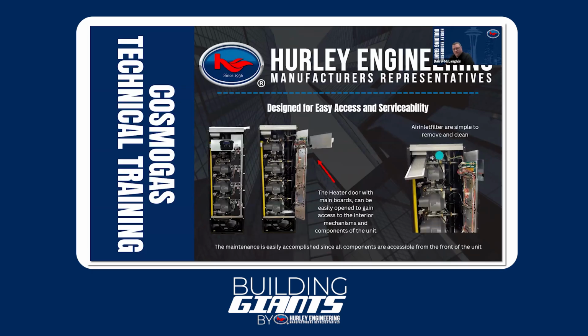So one thing that was super important to CosmoGas is serviceability, right? So everything they have is accessible from the front. You can see here in the picture on the left, we've got up to our 4 burners all stacked in at once. If a heat exchanger has to be replaced, there's 2 mounting bolts and it pulls right out. All of our burner safeguards, our flame controls here, are on the right-hand side as well. And if you need to service those, you can see on the next picture how that door swings open and you have access to all the wiring connections and controls. Our main interface is right on the front too, and that swings open so you can access it. There's nothing that you need to service on this equipment that you can't get to from the front.